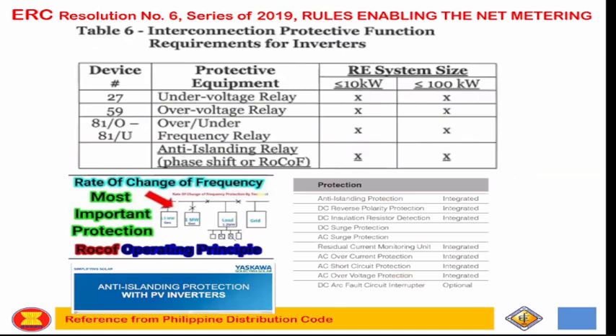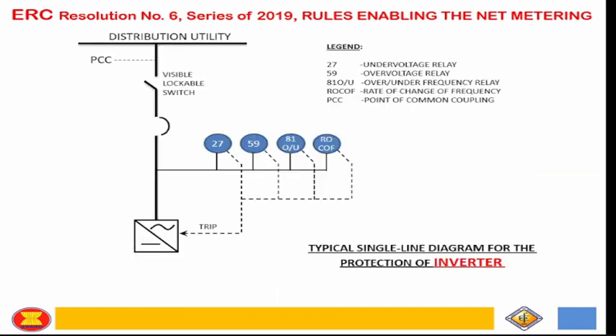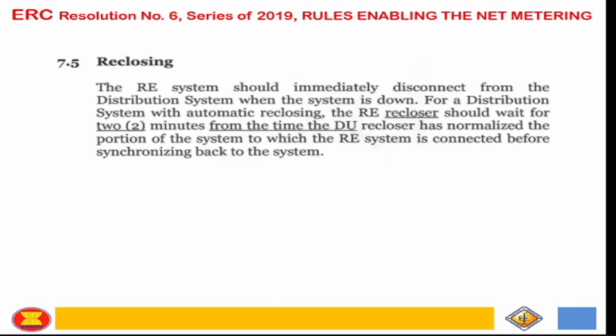Okay? And then for the interconnection protection requirement for inverters, yun yung mga solar natin, no? Ito, mayroong of course basic, no, over under frequency, over under voltage, and then the rate of change of frequency. Okay, so for the reclosing implementation, the RE system should immediately disconnect from the distribution system when the system is down. So you know, dapat may detection talaga na pag mawala yung distribution grid, automatically si DG mag-isolate, no. Then it's a normal isolation, no.